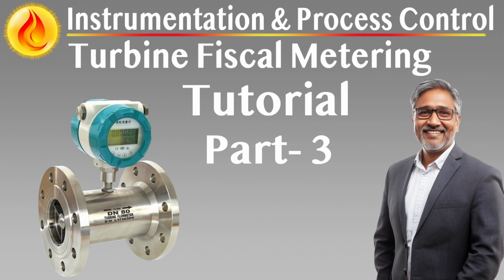When required, a precision laboratory-grade water cut analyzer must be supplied for calibration reference purposes. This analyzer must be certified with an uncertainty better than half the rated accuracy of the inline sensors. Although real-time water cut readings provide immediate feedback, contractual calculations of net oil quantity typically rely on composite sample analysis. As such, the role of the water cut meter is twofold. It offers operational awareness and acts as a supporting input to net quantity algorithms, subject to validation against sampled laboratory data.